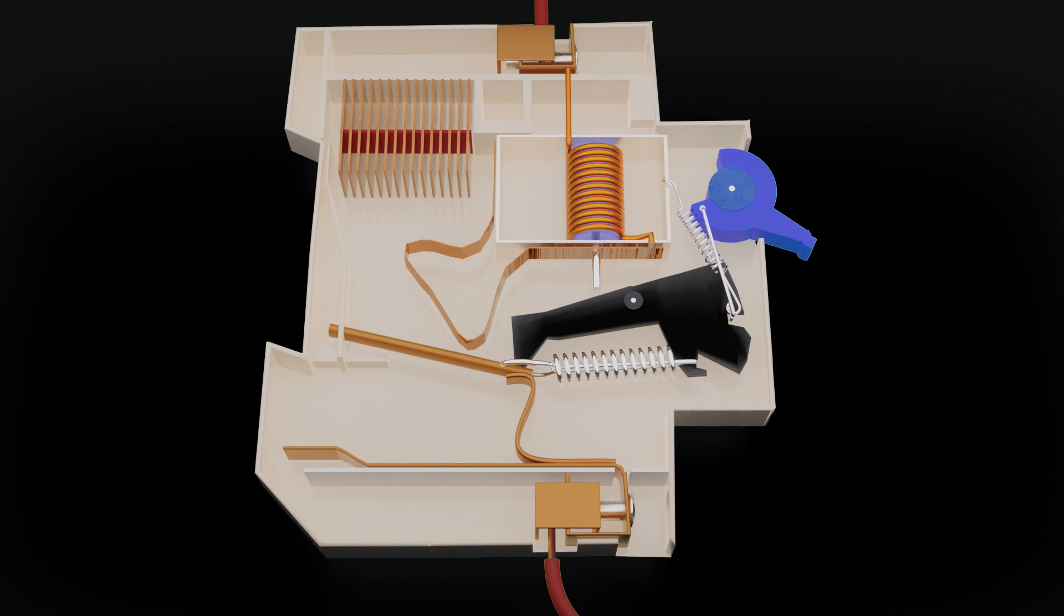Even if the circuit breaks, since high current flows in the circuit, current can also flow through the air. As a result, fire arc is formed. To solve this problem, arc runner is used in MCB. Small metal plates are kept parallel; it is called arc runner. As a result of this arc runner, the high current breaks down into small parts and arcing stops.